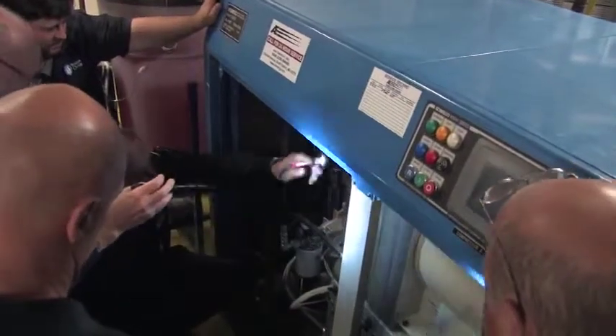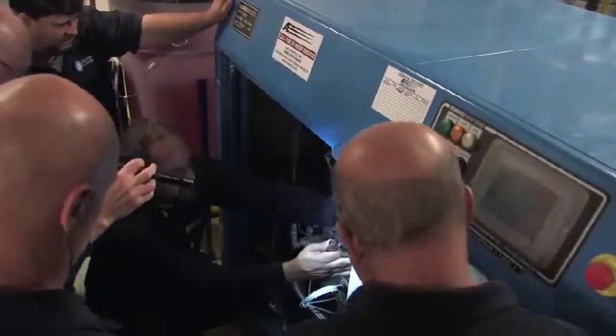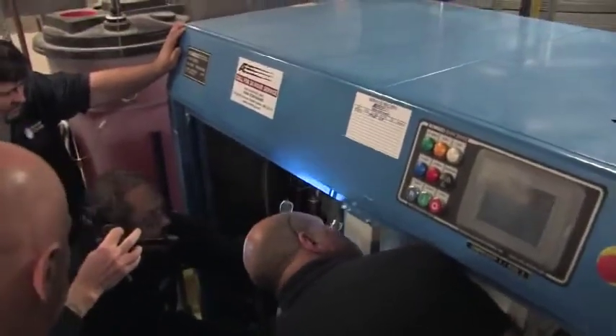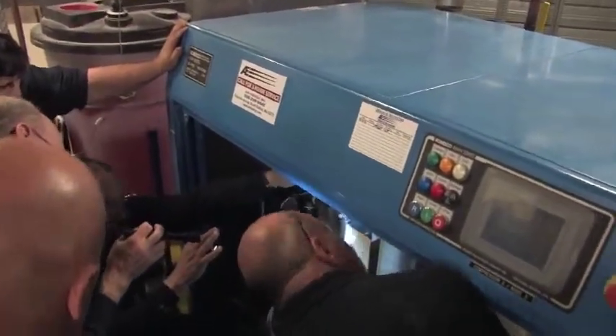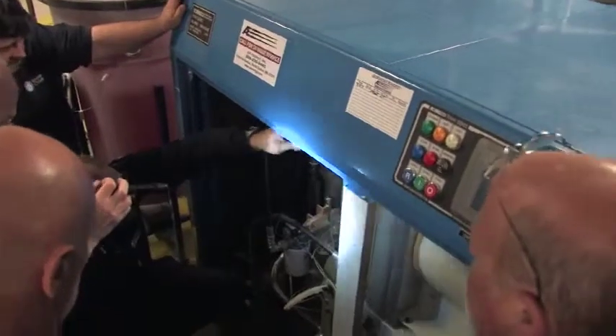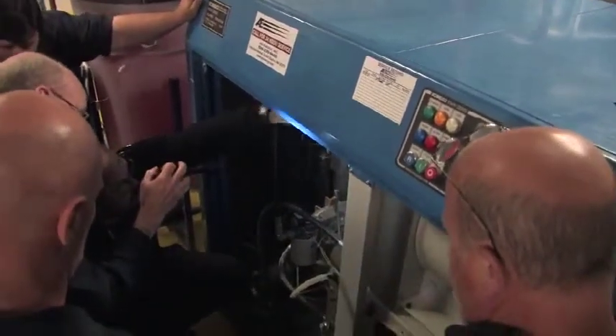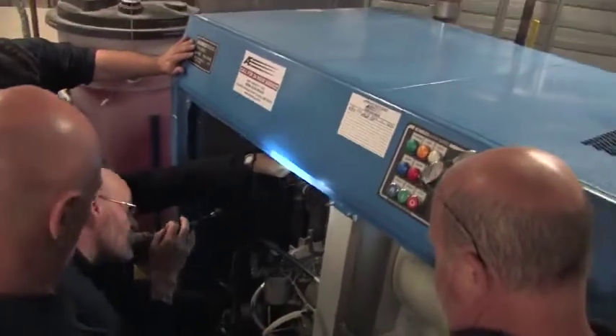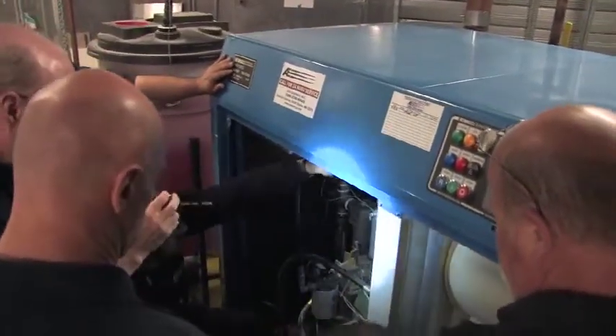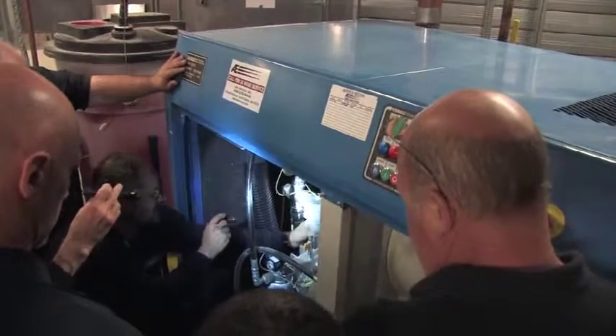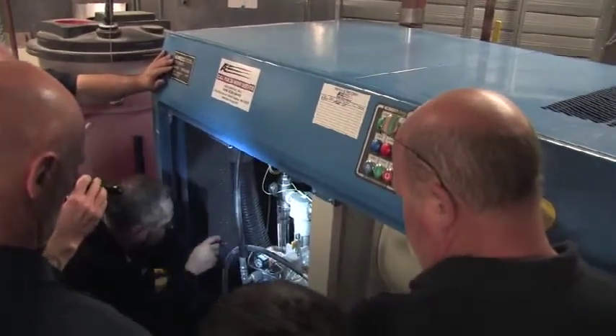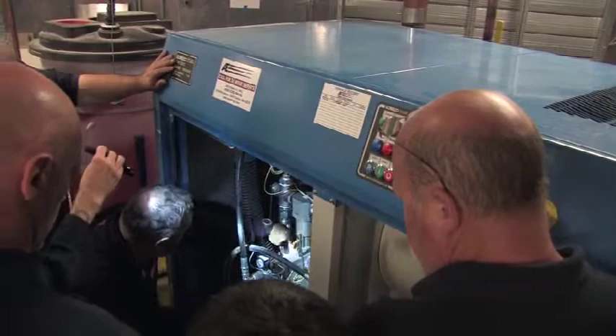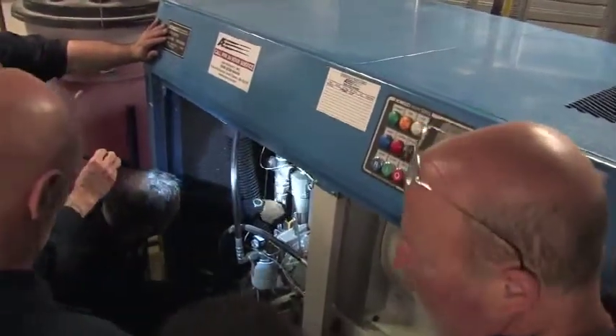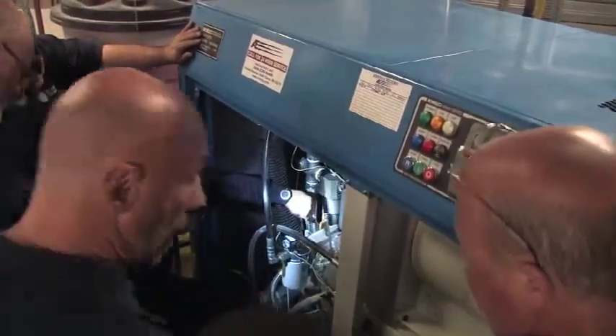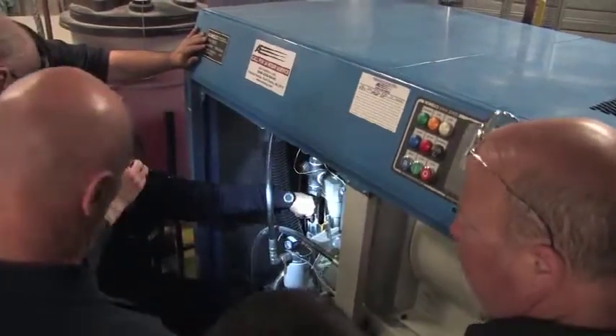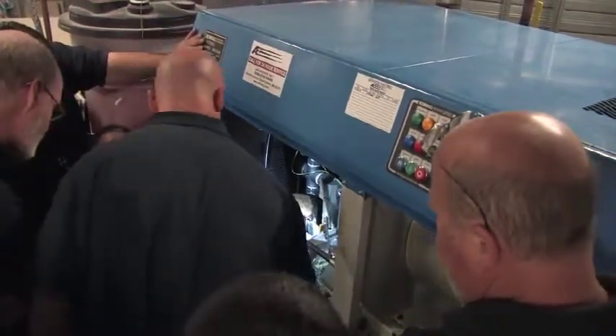Now there are three coolers with radiators here. First, six-inch here, this is the oil cooler. Second set in is the interstage or intercooler. And the last one, which has a vent to pull air in, is the aftercooler. So your air goes in through the interstage and hits this moisture separator. There's a solenoid drain on that down below. You'll also see there's a Y strainer just ahead of it and a check valve after it. So they actually put the check valve in there now. They didn't used to put those in.